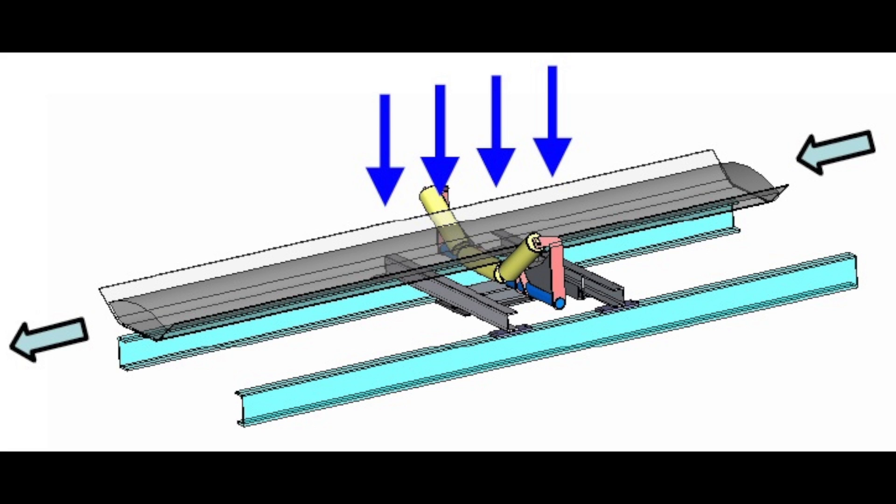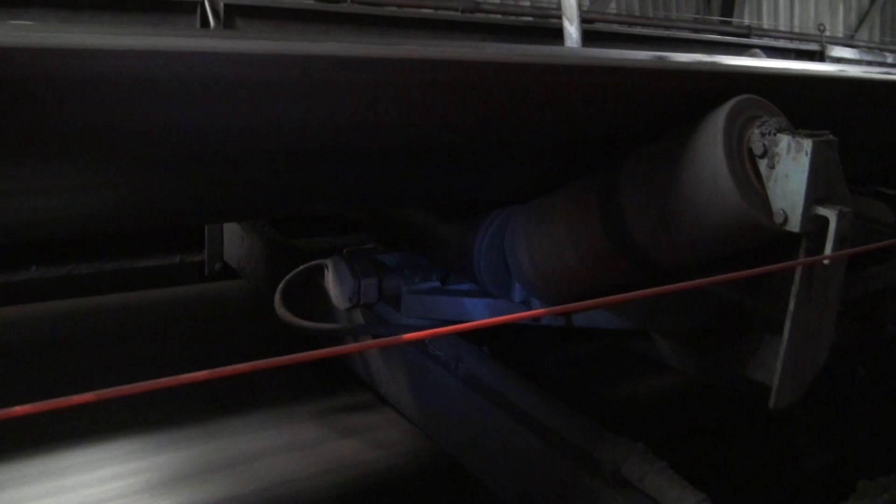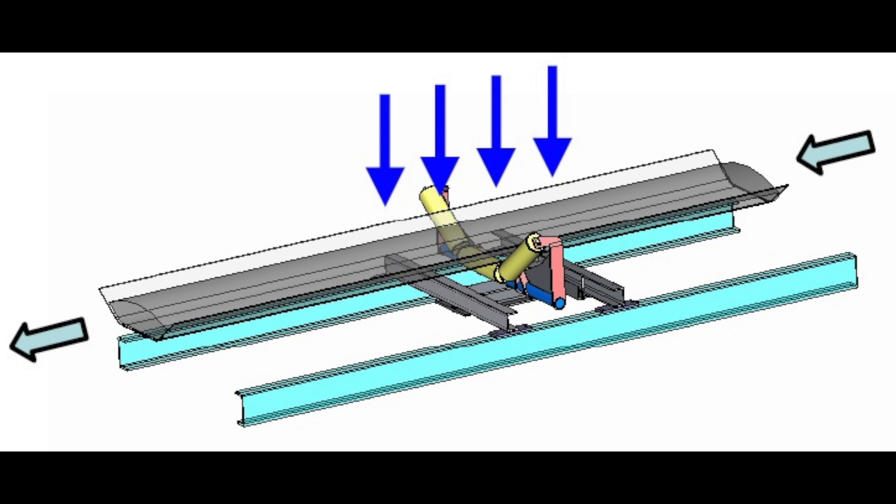The flat V-shaped, trough-shaped belt scale type VIB-EES is built around a set of high-precision rollers, mounted in a rigid and sturdy hot-galvanized steel frame. The material is entered onto the conveyor belt through the inlet. After the inlet, the weighing section must be placed as close to the inlet as possible. However, the material must stabilize on the belt and travel a minimum of two times the maximum belt width before crossing the weighing section.